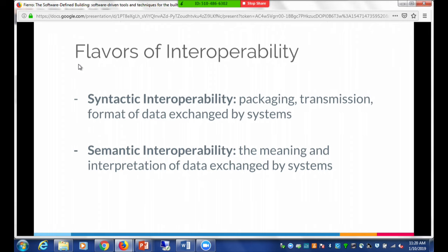The way we achieve this is through interoperability, which has two flavors. Syntactic interoperability is about what data looks like when two systems talk to one another—this is, to some extent, what BACnet tries to solve. If I have a controller and a damper, how do I say open the damper up? What it really says is how do I communicate some number to some point in your register file so you can open that up. It doesn't mean it's necessarily a damper—you have to know that ahead of time. But it does mean two systems can send data to each other without necessarily knowing what it means, just that I'm sending you the number 3.